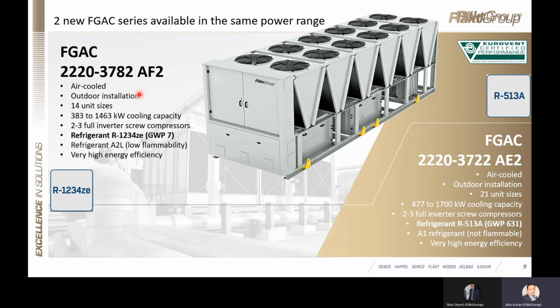These are available with two refrigerants, R-1234ze and R513A. Let's start with R-1234ze. This is one of the best in-class refrigerants available today, with a lower GWP of 7. And we have 14 unit sizes on this, starting from 380 to 1463 kilowatts, with 2 or 3 full inverter screw compressors based on the capacity.